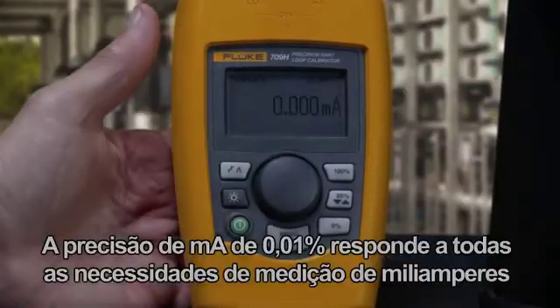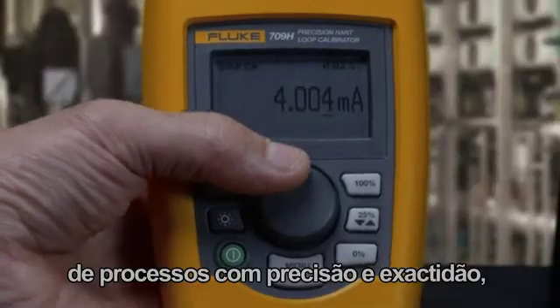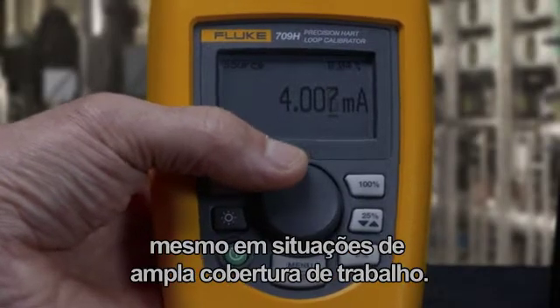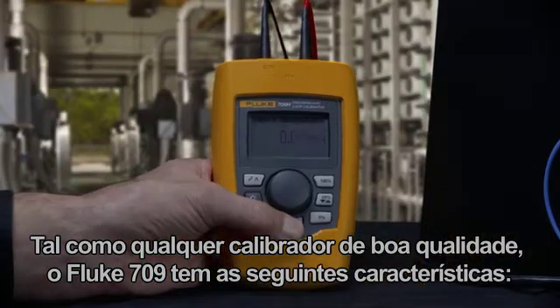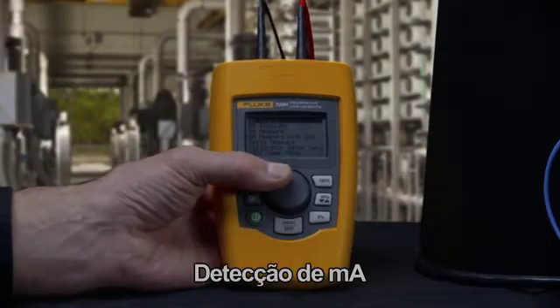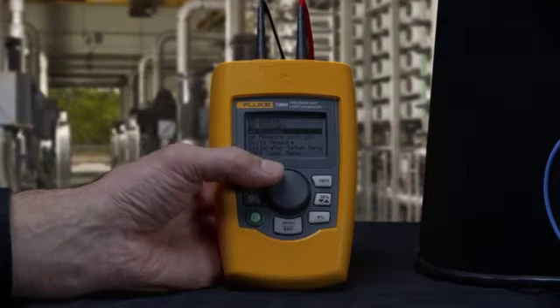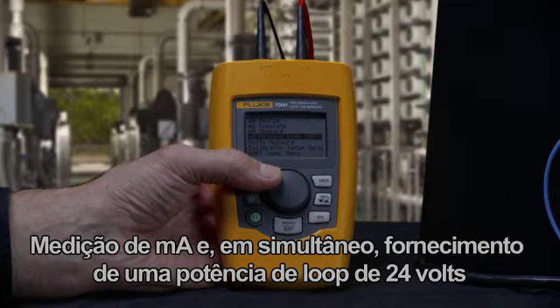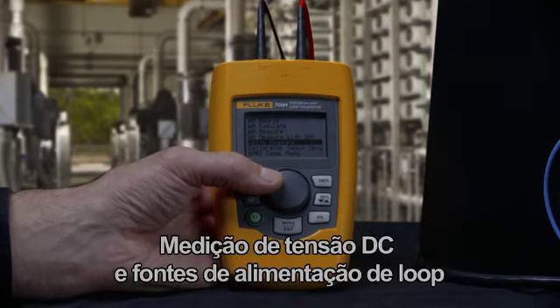The 0.01% milliamp accuracy meets any process milliamp measurement need with precision and accuracy for wide workload coverage. Like any good loop calibrator, the 709 can source milliamps, simulate milliamps, measure milliamps, measure milliamp while providing 24-volt loop power, and measure DC voltage and loop power supplies.